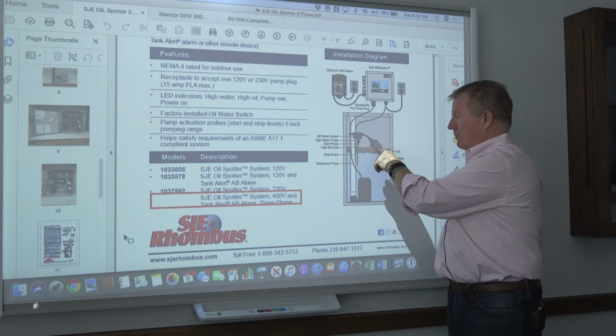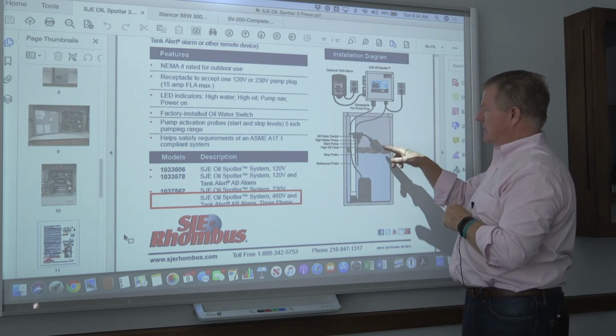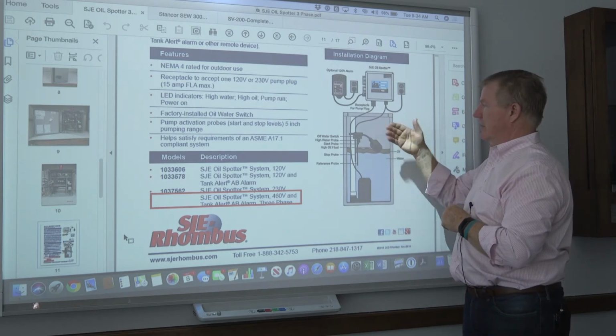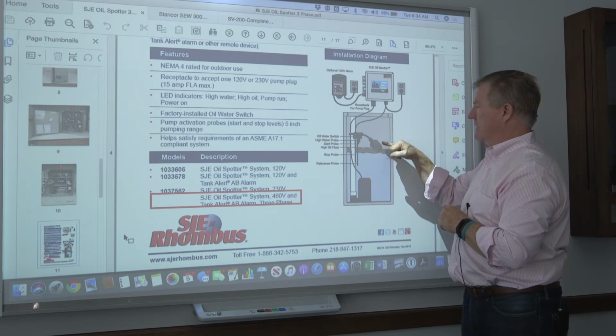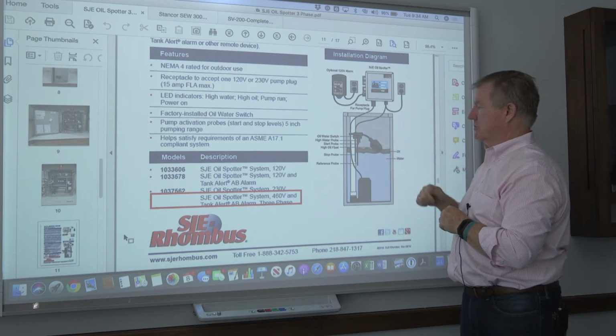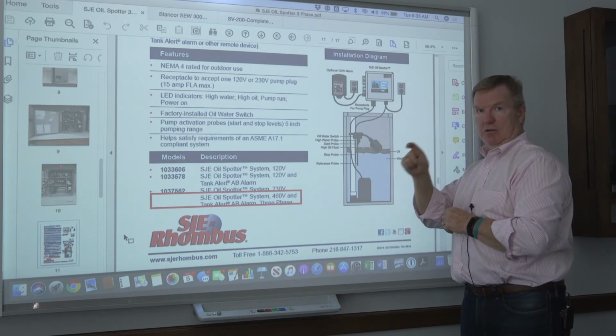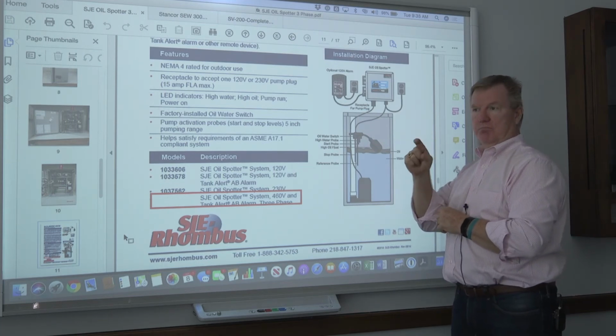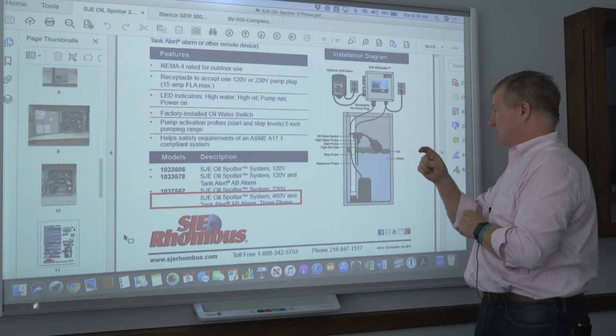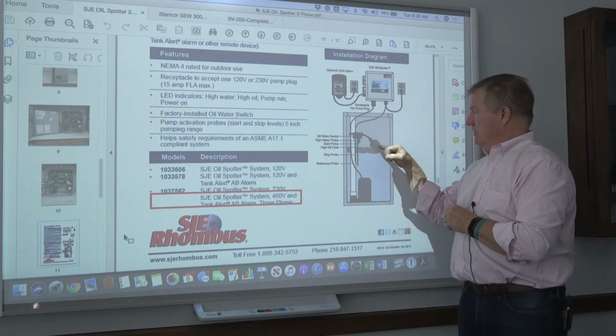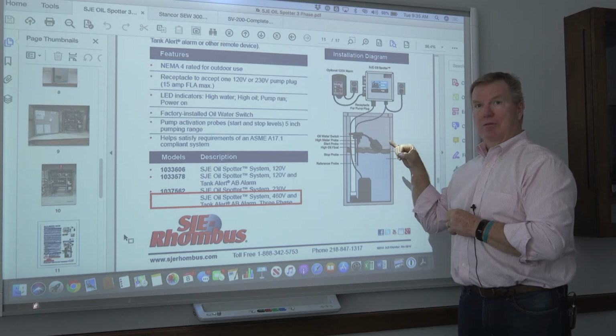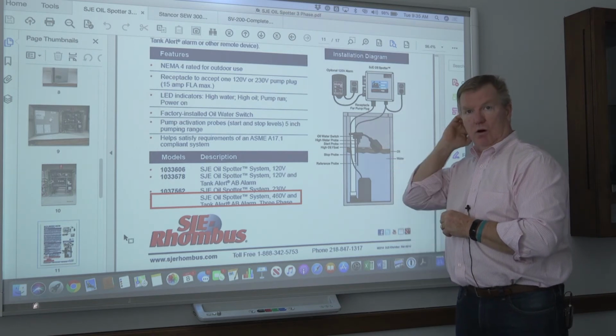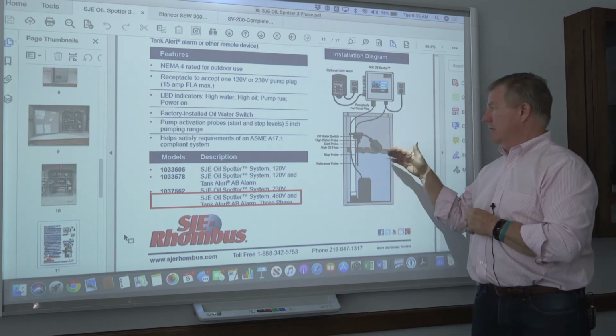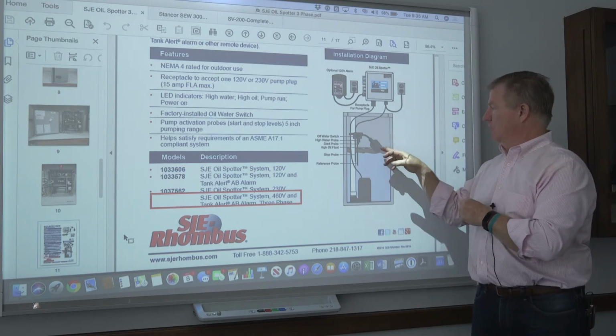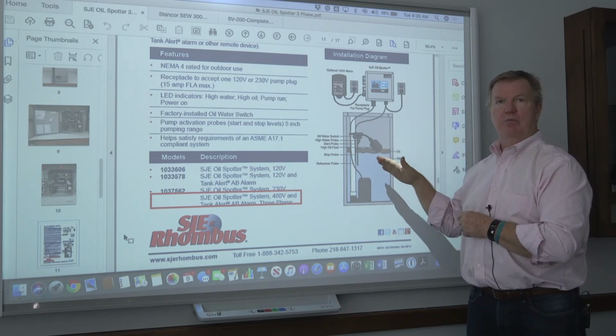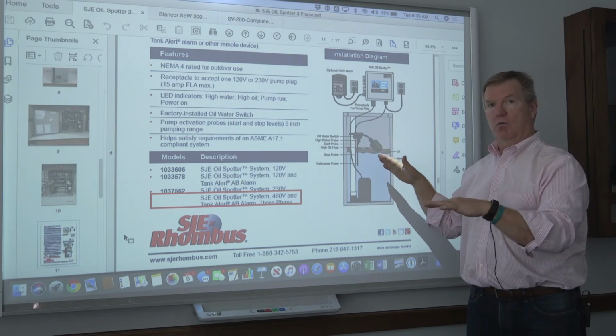So what the float does is, this float is designed to trip when the level gets above the start probe by a certain number of inches or millimeters above the water level. So this floats on top of the oil rather than on top of the water. So it's designed so that normally this float would stay in the down position if there's no oil on top of the water.